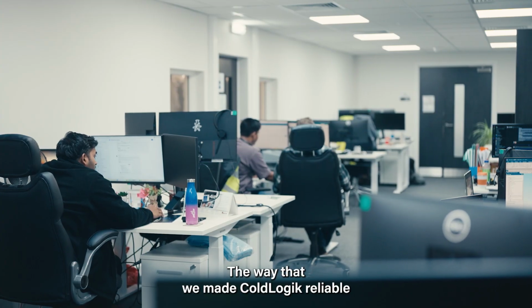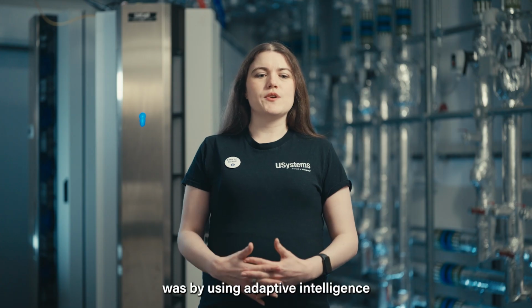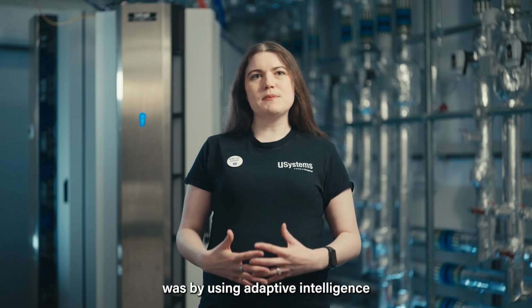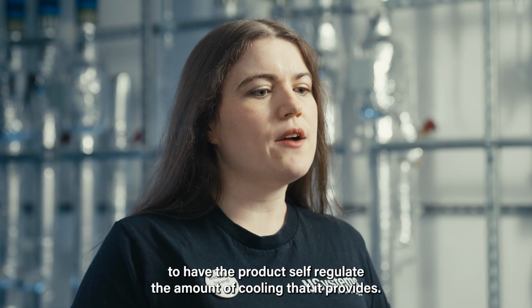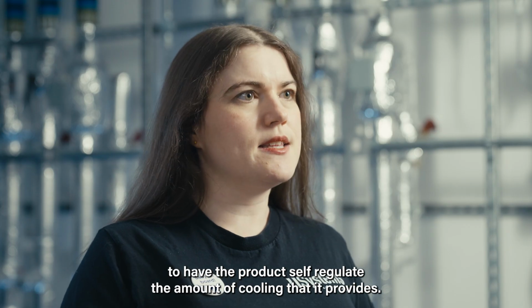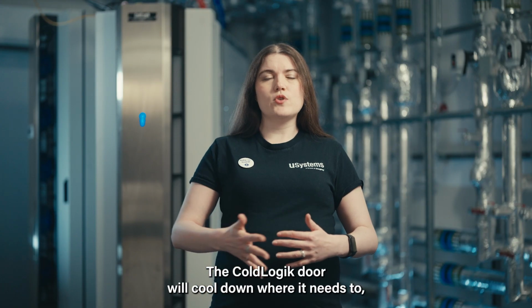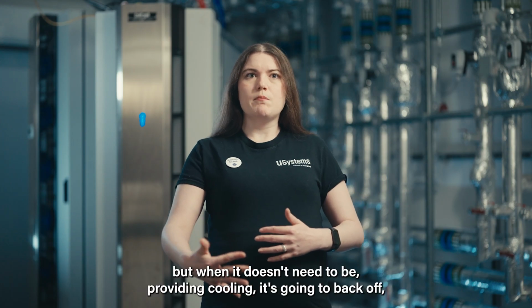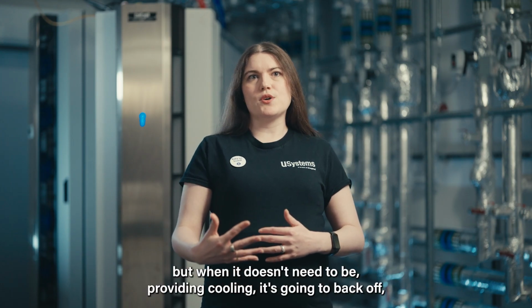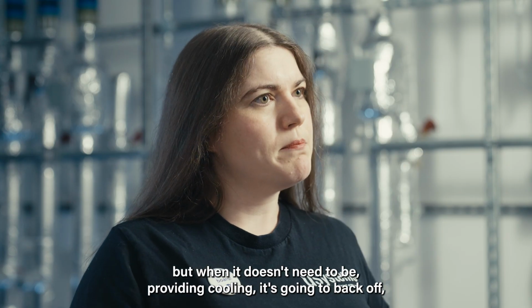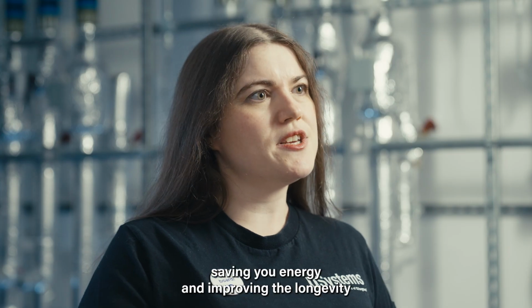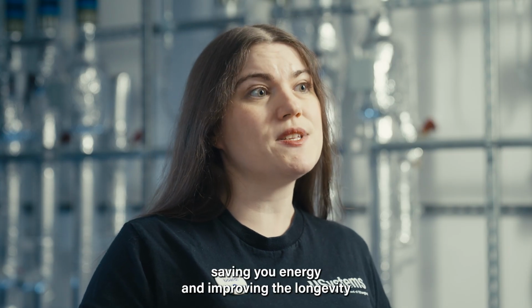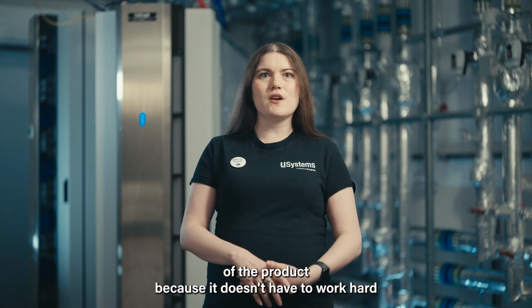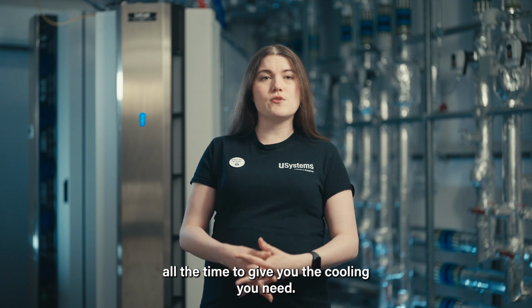The way we made ColdLogik reliable was by using adaptive intelligence to have the product self-regulate the amount of cooling it provides. The ColdLogik door will cool down where it needs to, but when it doesn't need to be providing cooling, it backs off, saving you energy and improving the longevity of the product, because it doesn't have to work hard all the time to give you the cooling you need.